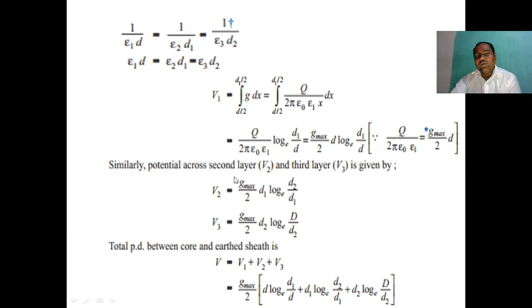This is very important: as the permissible values of g maximum are peak values, all the voltages in the above expression should be taken as peak values and not RMS values. If the maximum stress in the three dielectrics is not the same, then V = G1 maximum by 2 d log base e d1 by d + G2 maximum by 2 d1 log base e d2 by d1 + G3 maximum by 2 d2 log base e capital D by small d2.